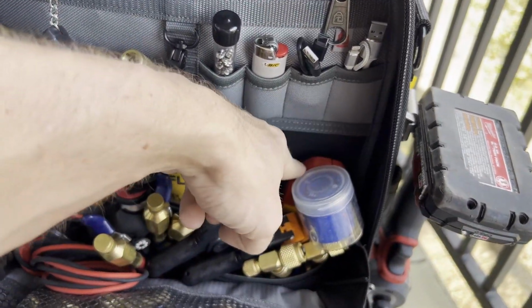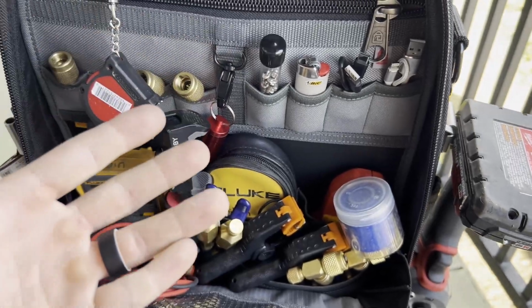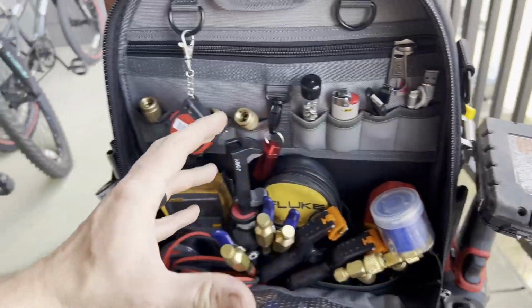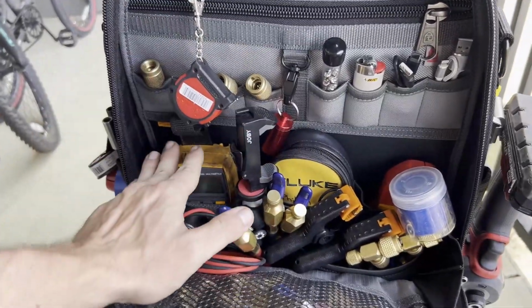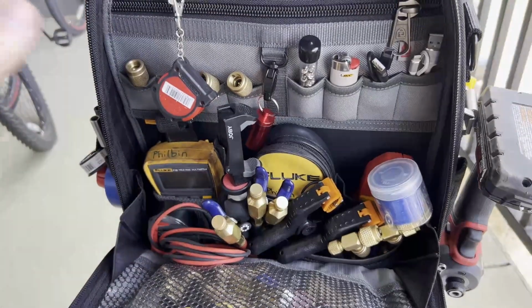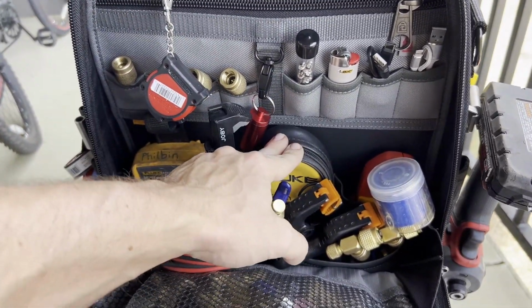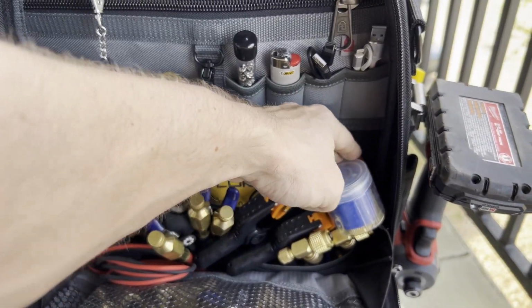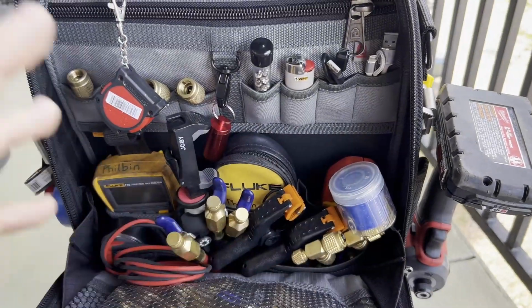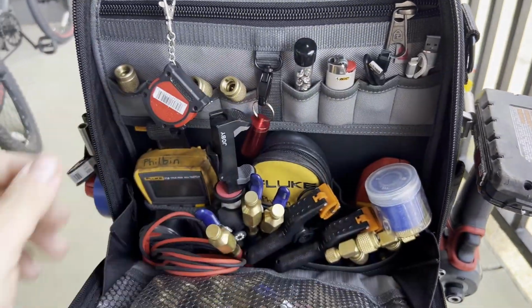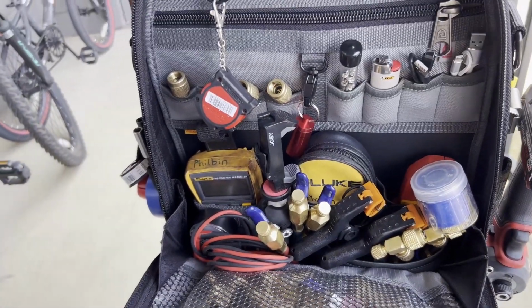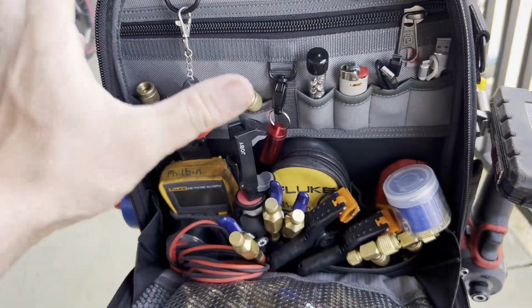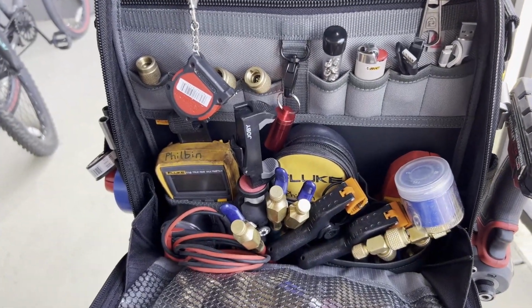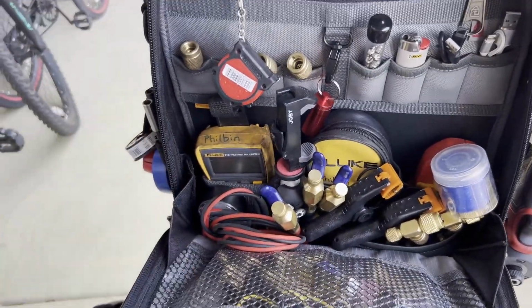I carry 2 amp clamp meters so I can check multiple amperages on different components at one time. So I'll be checking voltage here, I'll have 3 meters out at one time. I'll have this hooked up to a blower motor, this hooked up to condenser fans, rotate between my compressors so I can monitor amp draws on different things. I don't like just carrying 1 meter. I'll set them up in 2 or 3 different areas of the electrical compartment and look at all my data at once.